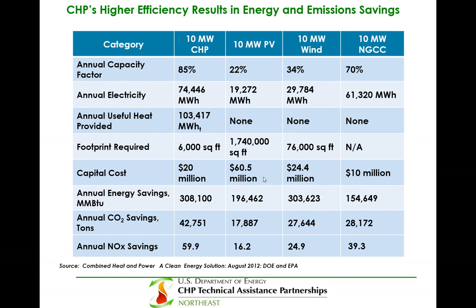I think the strongest takeaways here are, first of all, the total system efficiencies. CHP runs at about 75% total system efficiency, versus about 50% for gas. The annual capacity factor for CHP is far greater than for renewables. And most important, the annual useful heat produced—this is the essence of CHP: capturing and reusing waste heat productively for space heating, hot water heating, driving absorption chillers, industrial process heating, sterilization, or laundries. CHP does this at a fairly low capital cost compared with some renewable technologies.